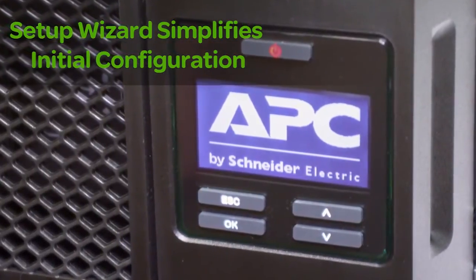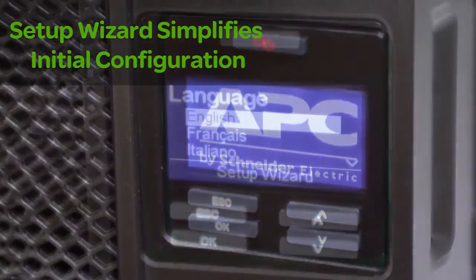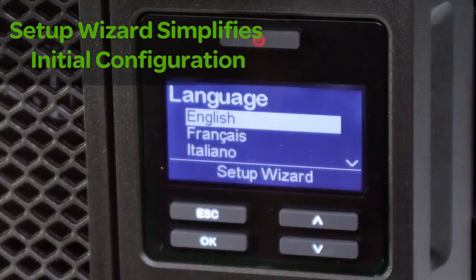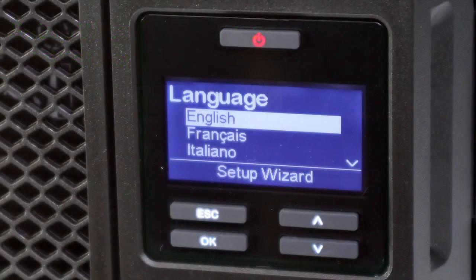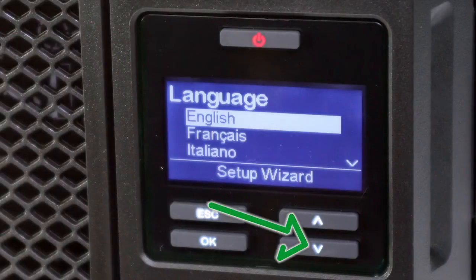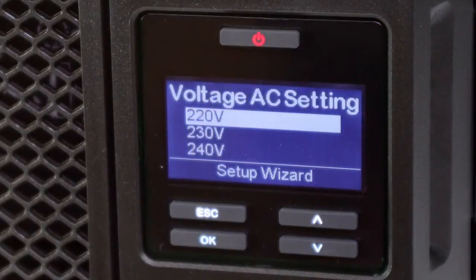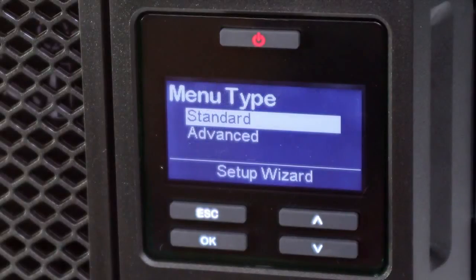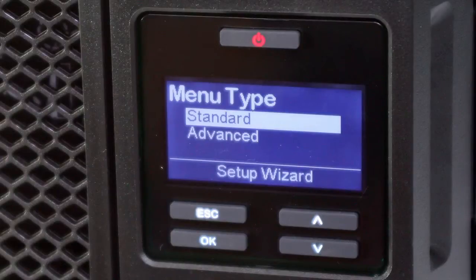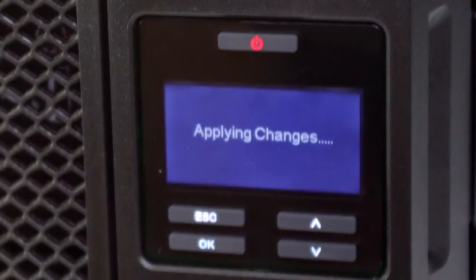The wizard walks the user through three configuration screens. The first screen asks the user to select a display interface language. Use the arrow keys to select the desired language and hit the OK button. The second screen asks the user to select the voltage setting. The third screen asks the user to select the preferred menu type. The standard menu offers the options most commonly used by customers, while the advanced menu provides access to all configurable options. The UPS won't turn on until all of the settings have been configured.